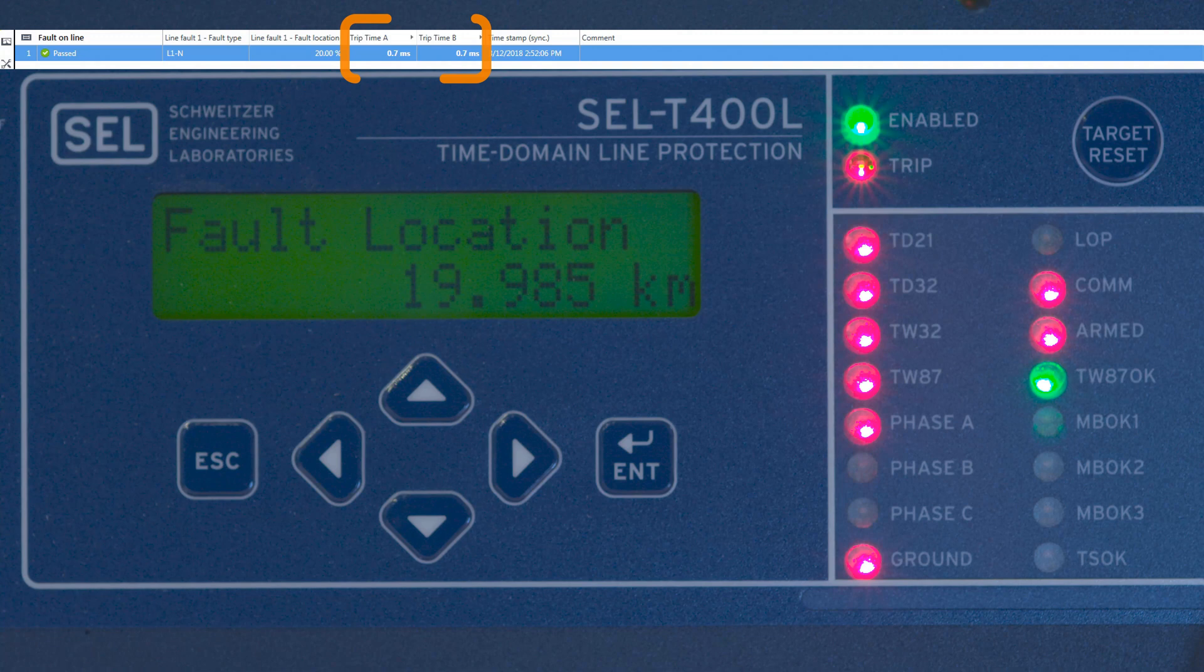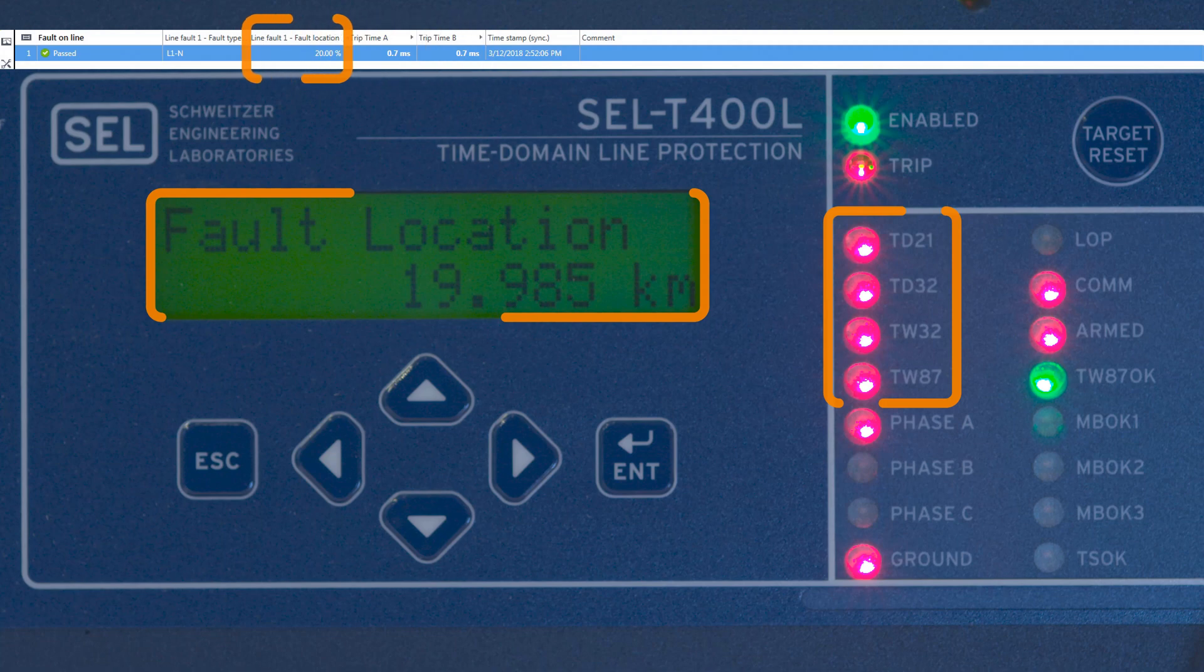The relays have tripped with ultra-high speed. All of the elements have picked up and the fault location that they are displaying is the one that I defined in RelaySim Test.